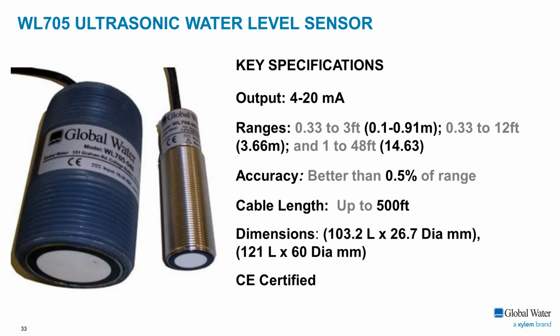And you can see here we have the cable length, where if we start getting over 500 feet, we're going to need to put in a booster. So we want to boost up the signal to make sure we have power to ensure the accuracy coming from the ultrasonic sensor. The outputs here are 4 to 20 milliamps, as well as RS-485 output. And if you use RS-485, you can go up to 4,000 feet, because the RS-485 signal can travel a huge distance without any electrical breakdown.